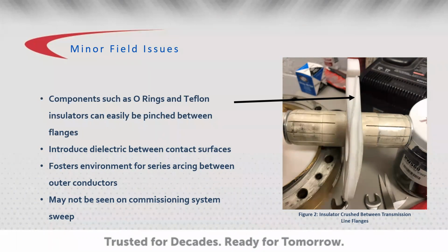The pinched material introduces an undesired dielectric between the outer conductors, minimizes the contact surface between components, and creates a strong potential for series arcing. Depending on the magnitude of the contact surface separation, as well as the location of the pinched component, this may not be diagnosed during commissioning or a sweep.